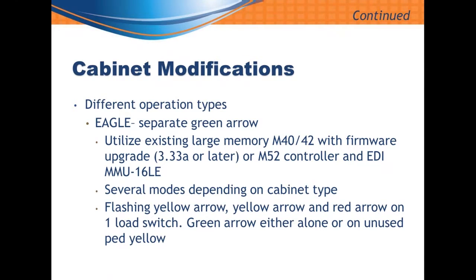That was a cost savings — we didn't always have to buy a new controller. But looking back five or six years into the project, I would recommend replacing the controller. The M42 is a good controller but requires replacing EPROMs for upgrades and has no capacity to transfer the controller program through a data key or flash drive. Since the programming is rather complicated, it's good to have an easy way to transfer it. Also, since we originally did this, the MMU-2 standard that NEMA developed took everybody's different flashing yellow arrow modes and assigned a letter type for each one, meaning you could now use an EDI MMU or a Reno MMU in most flashing yellow arrow designs.